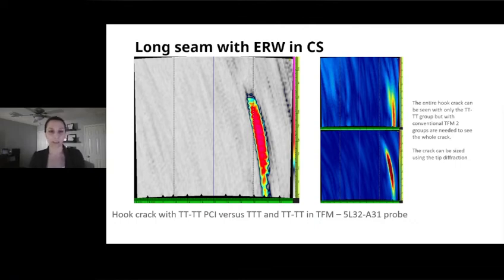That's the flaw we looked at earlier. This is actually a hook crack in a long seam ERW weld in carbon steel. The entire hook crack can be seen using only one mode. The 4T mode was used here. Where conventional had to look at two different modes to be able to size this hook crack properly. So that's also a benefit, being able to see a bit more, but also size more accurately by using the tip diffraction.